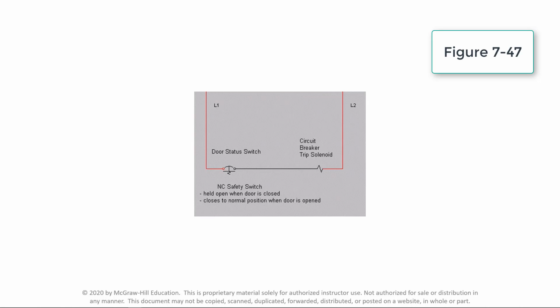In this simulated application, the NOT logic function is used to prevent accidental contact with live electrical connections. The normally closed safety switch operates by detecting the opening of guards, such as doors and gates. Contacts of the normally closed safety switch are held open by the shut door. When the door is open, the safety switch returns to its normally closed state and the trip solenoid of the circuit breaker is energized to remove all power from the circuit.